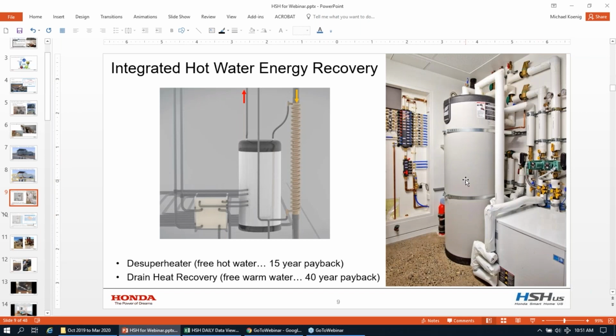But the hot water tank, this is just an interesting sidebar lesson. In our original design, we had a very, very clever layout, and you can sort of see it here. This pipe that comes from the top of the hot water tank actually comes back down and into the side of the hot water tank. And you say, why is this thing piped into itself? It was a very clever design; we were trying to stratify the tank. In order for that de-superheater to work more effectively, we needed a larger temperature difference. So we said, we can get a larger temperature difference if we can separate the heat energy that's in the tank, and keep the top of it hotter and the bottom of it cooler.